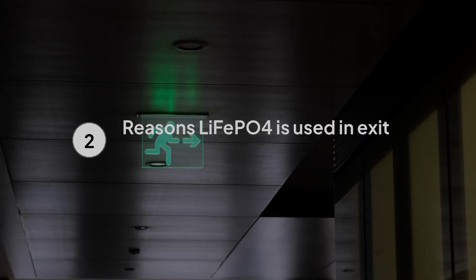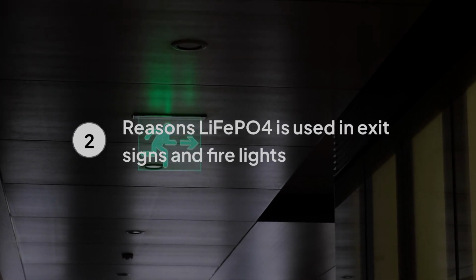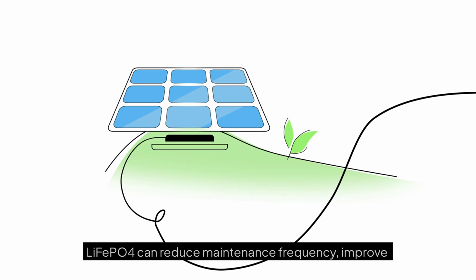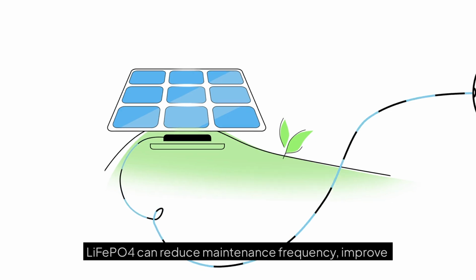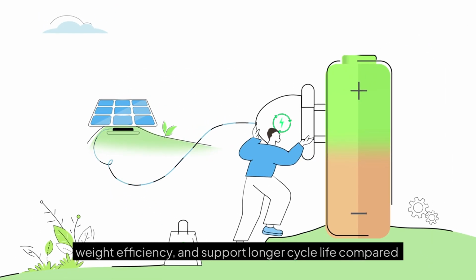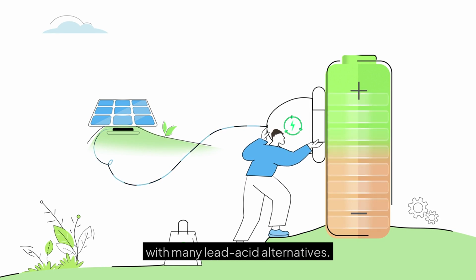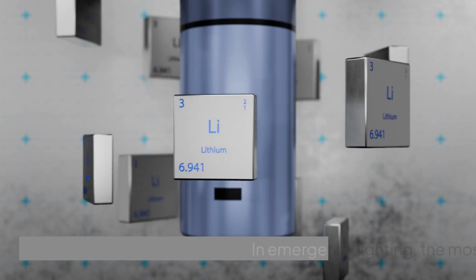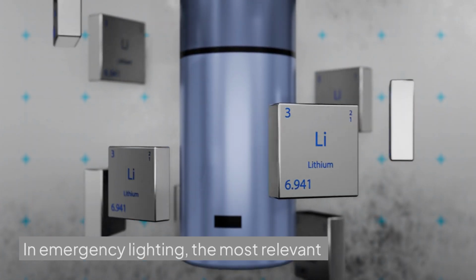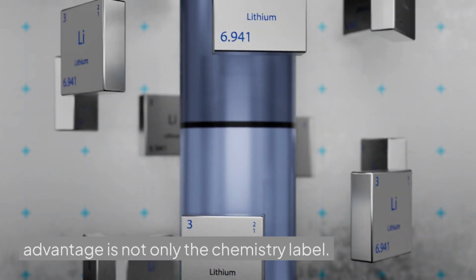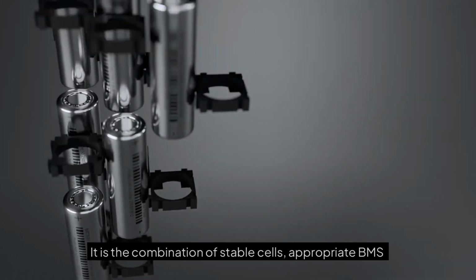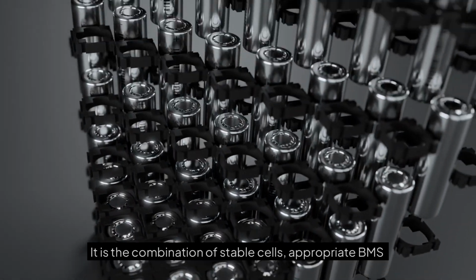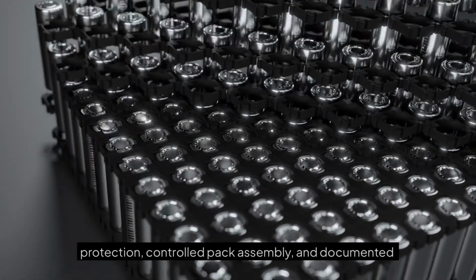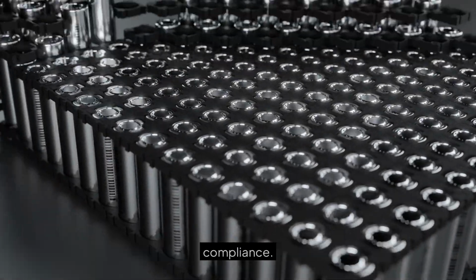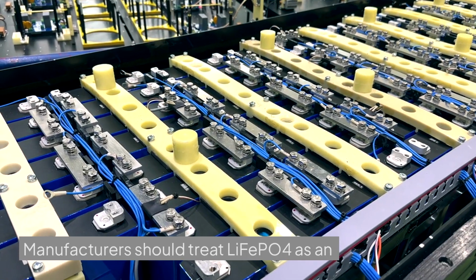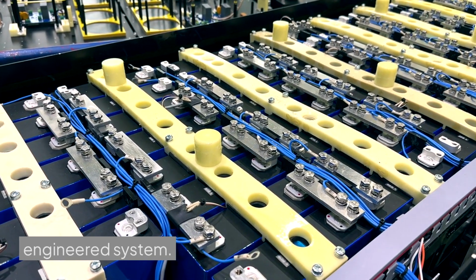2. Why LiFePO4 is increasingly used in exit signs and fire lights. LiFePO4 can reduce maintenance frequency, improve weight efficiency, and support longer cycle life compared with many lead-acid alternatives. In emergency lighting, the most relevant advantage is not only the chemistry label. It is the combination of stable cells, appropriate BMS protection, controlled pack assembly, and documented compliance. Manufacturers should treat LiFePO4 as an engineered system.